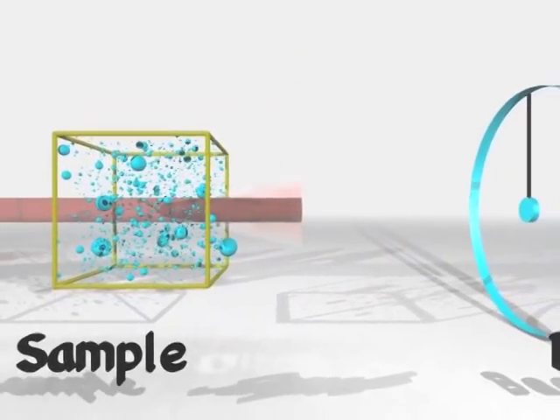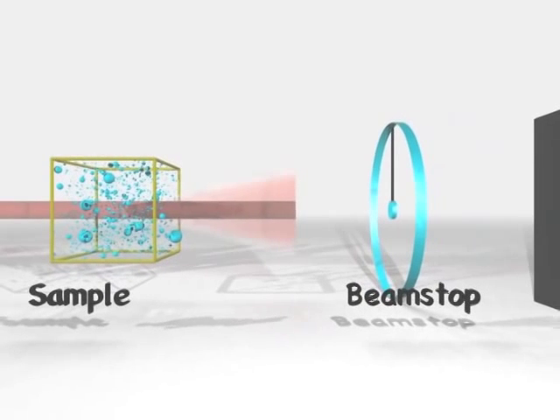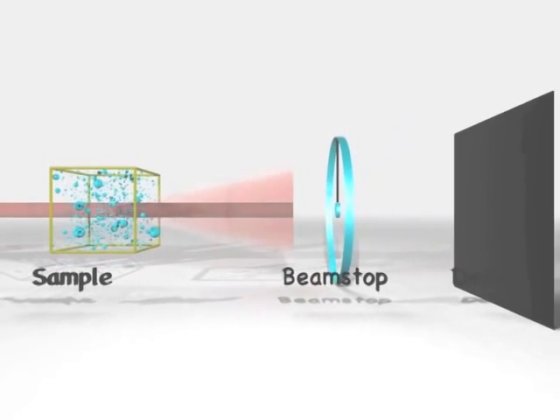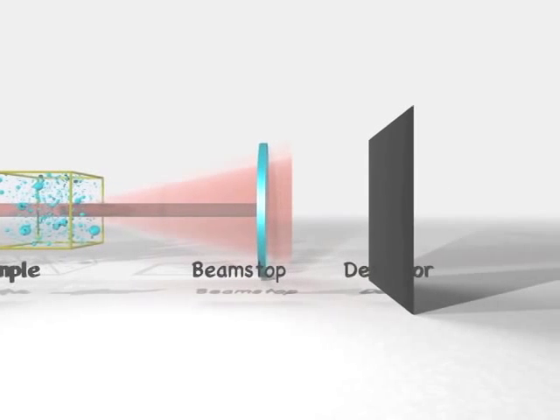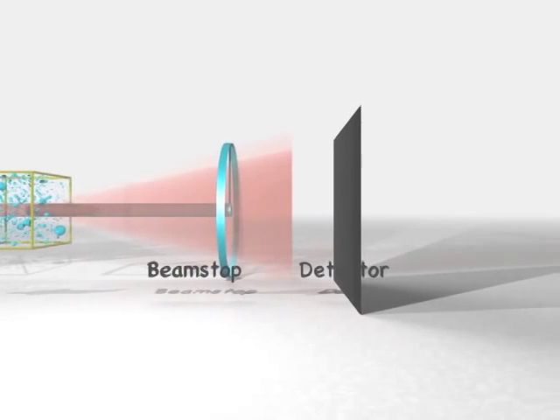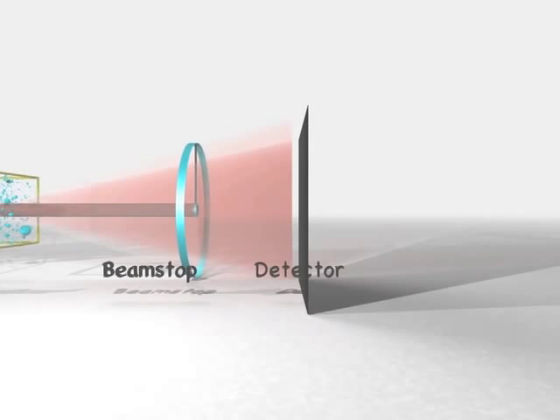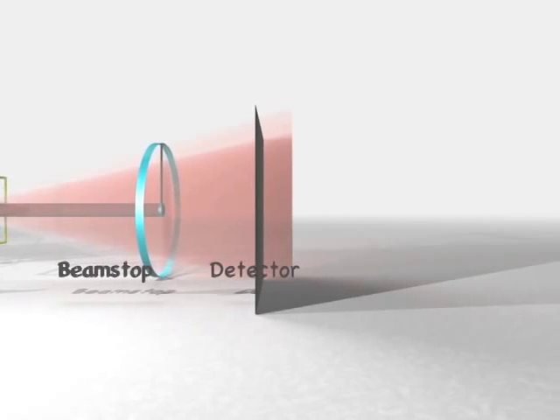To prevent the main beam from damaging the detector, the beamstop is designed to cut away the main beam and to let the scattered radiation pass through. The scattered radiation will then fall onto the detector, which will count the radiation.